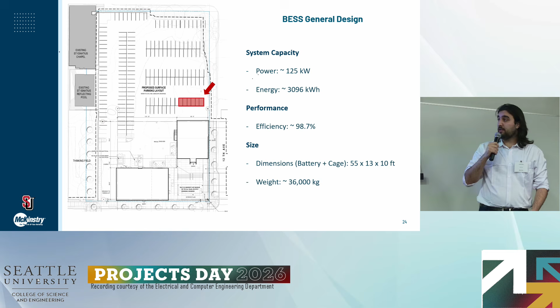Now, with that battery system in place, how do we decide when and how it acts? To do this, we modeled a predictive control algorithm within Excel that runs through a 3-step cycle every single day. At the beginning of every day, the control strategy will try to predict the electricity use of the day ahead. This is done utilizing the past week's worth of electrical consumption data, as well as forecasted weather and demand patterns. Using all of that information, it will then set a daily internal demand limit for itself, which is basically a ceiling capping off how much electricity the building is allowed to pull from the electrical grid for that day. With that limit in place, the battery will then charge and discharge accordingly, ensuring that the building's electrical draw from the power grid remains below that internal limit.